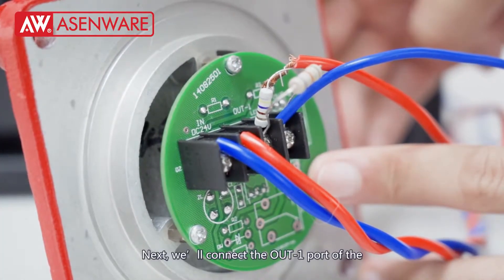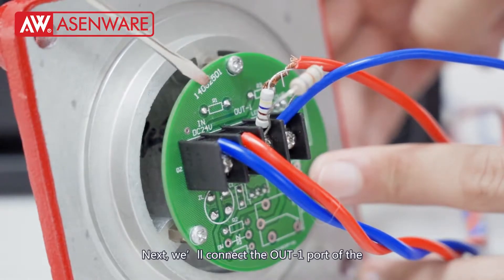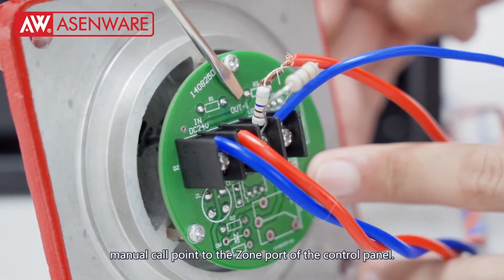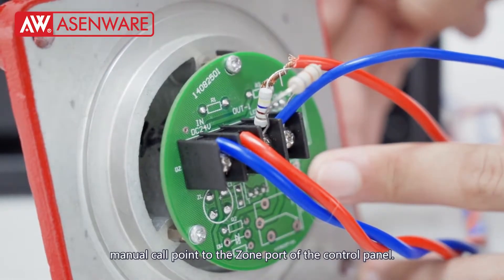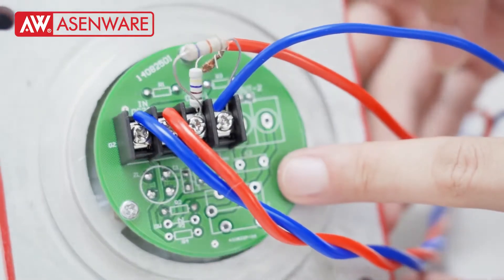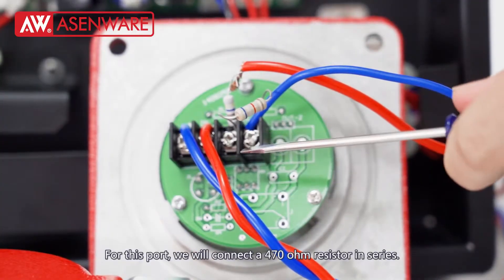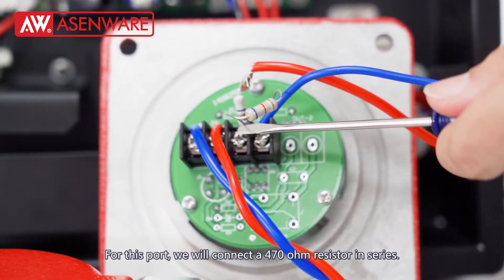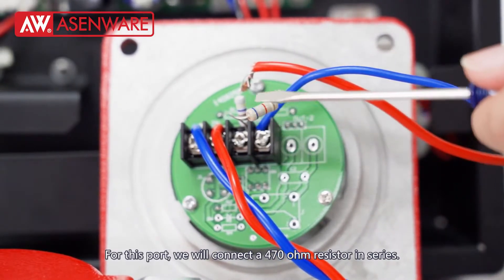Next, we will connect the OUT-1 port of the manual call point to the zone port of the control panel. For this port, we will connect a 470 ohm resistor in series.